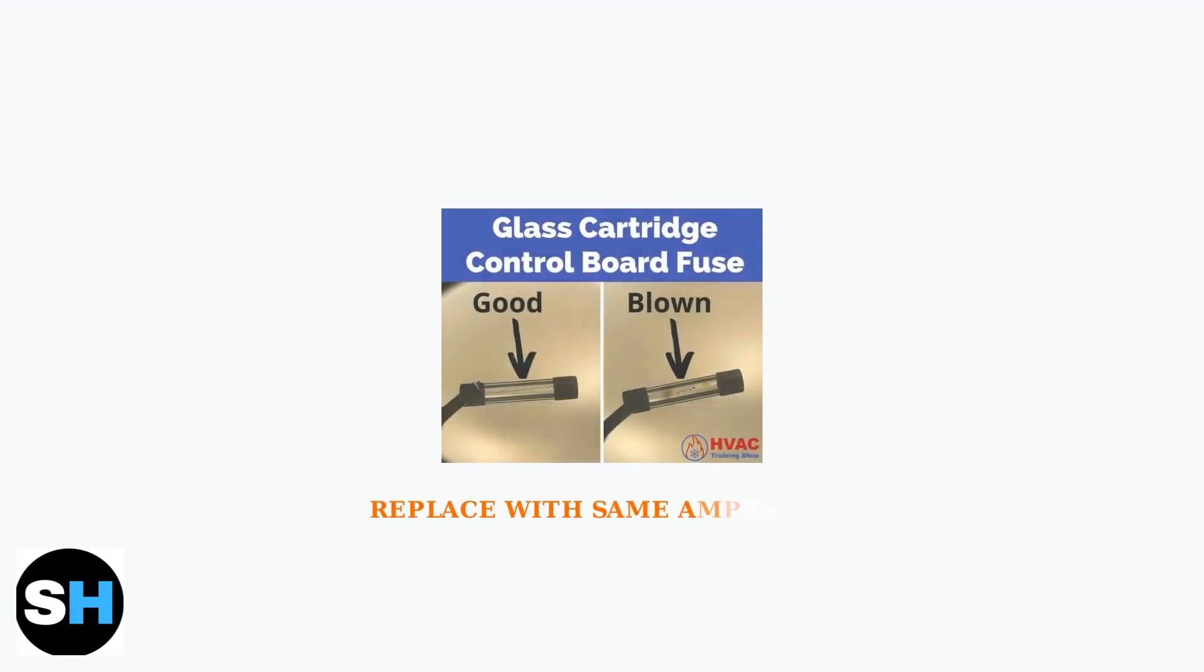Open the furnace panel and check the safety switches and fuse. A blown fuse will have a broken wire inside the glass cartridge. Replace it with the exact same amperage if blown.